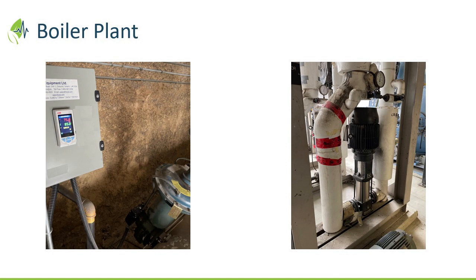So there's new solenoid valves, something like that? We're looking to encourage a more robust solution than a solenoid. They can be problematic, but yes, it'd be an on-off valve. And will there be a variable frequency drive on the feed water pump or not? One can look towards that. Traditionally, because of all those bypass orifices, the payback's been neither here nor there. But as you implement more technology, you can get feedback from the system to say, I've got so many boilers, set the pump to here. So that is something you can consider in the future. But these are the stages I think you should know.